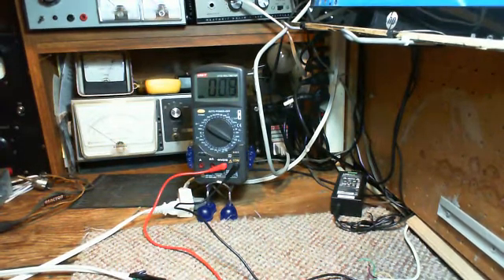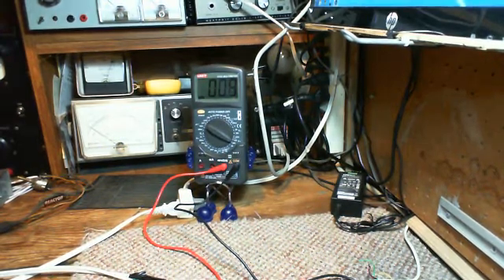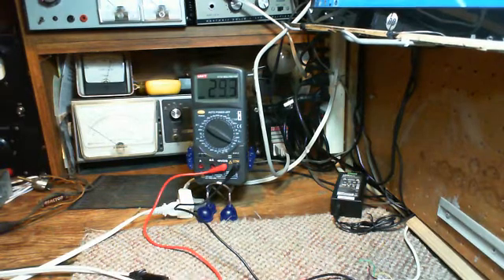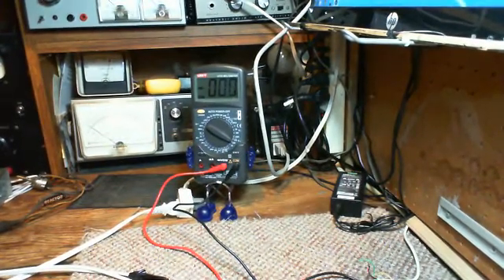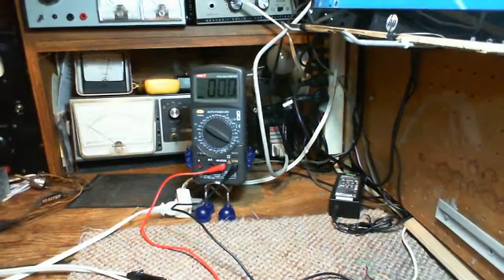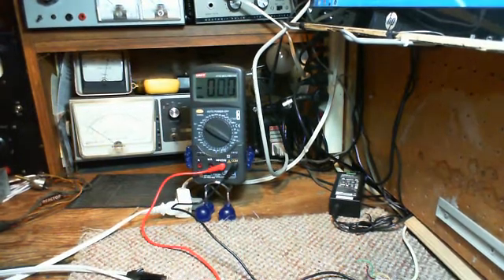Okay, so there's now a little over 125 volts. The readings are about 62 volts. This is telling me that these are ungrounded. If one of them was grounded, then the reading would have been zero on one connection, and the other would have been the full voltage — 120 volts.